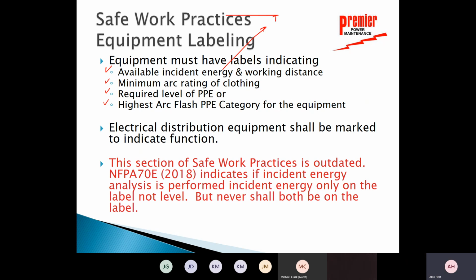Okay, we have to have the incident energy. So the incident energy is going to be in calories per square centimeter. And to us, the key is 1.2 calories per square centimeter. Any equal to 1.2 calories per square centimeter or greater means that you are required to have arc flash protective clothing on. 1.2 calories per square centimeter is the onset of a second degree burn, and we're supposed to be protecting you from that second degree burn. So, incident energy, our big key is 1.2, you've got to have clothing on of some kind.